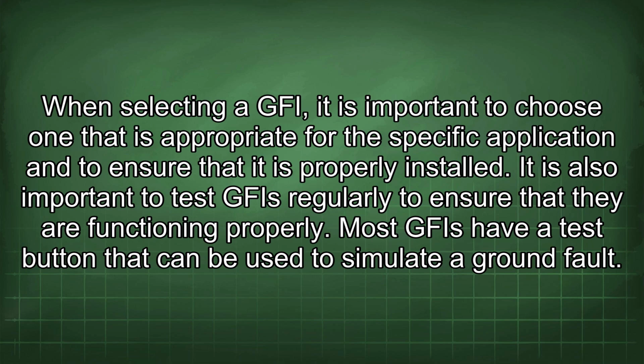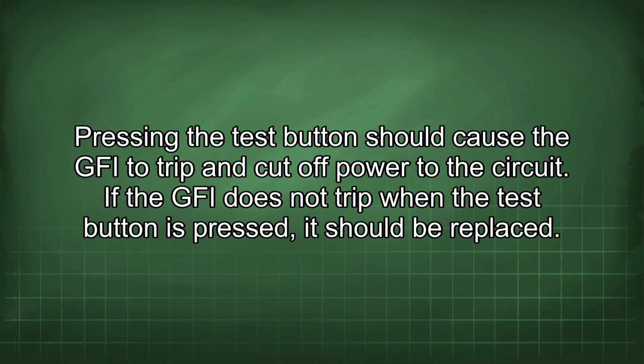It is also important to test GFI regularly to ensure that they are functioning properly. Most GFI have a test button that can be used to simulate a ground fault. Pressing the test button should cause the GFI to trip and cut off power to the circuit. If the GFI does not trip when the test button is pressed, it should be replaced.